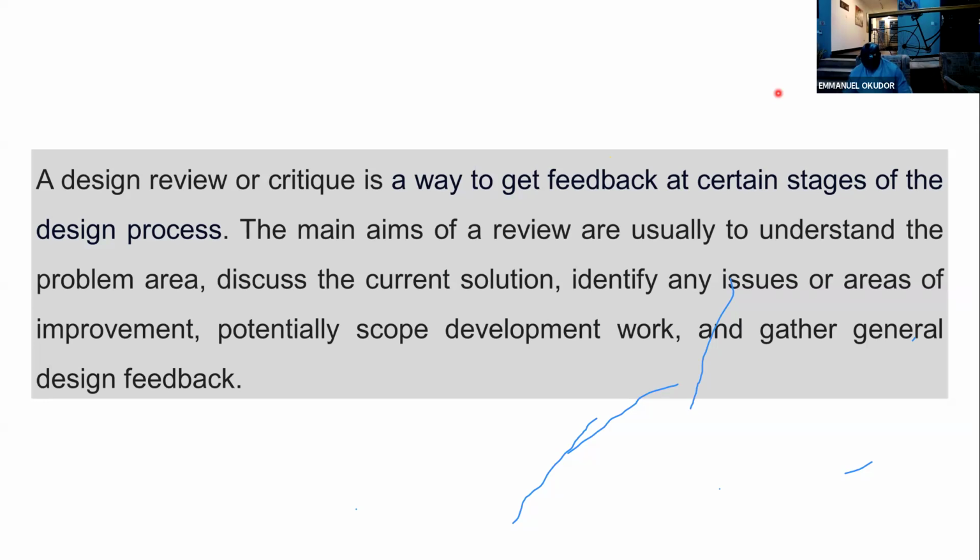Now, I have done over 95, I'm chairman to over 95 HAZOPs or PHAs using the HAZOP technique for different companies. Now, one common flaw is the fact that a whole lot of companies try to use PHA as a replacement or as a basis to do engineering design review.